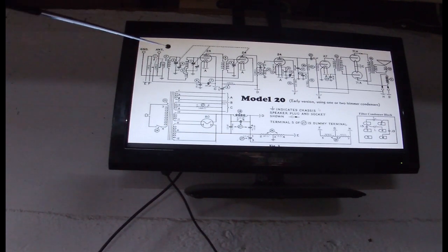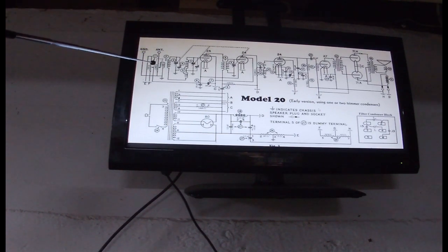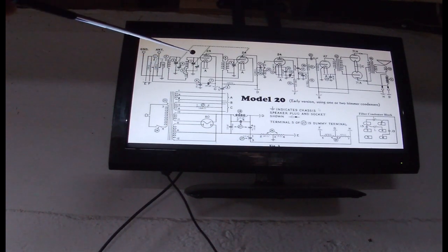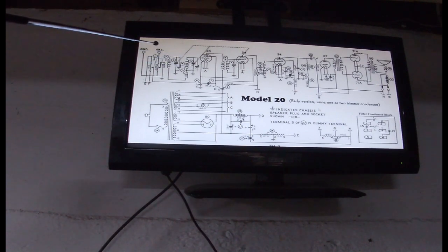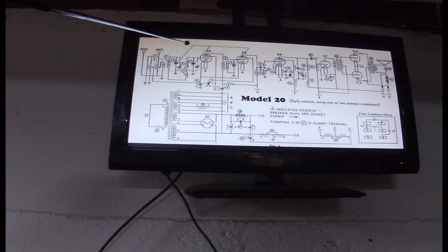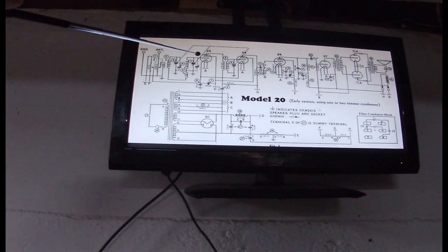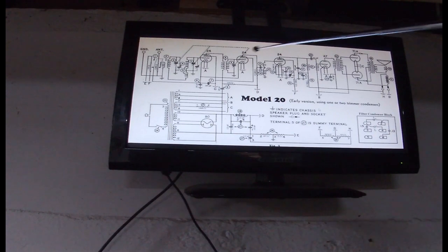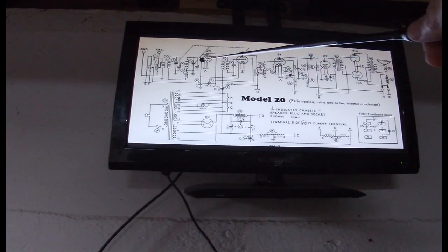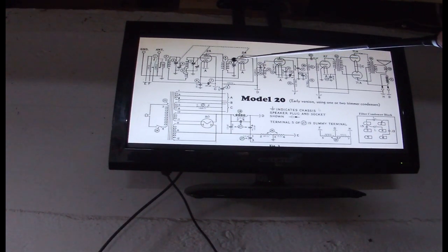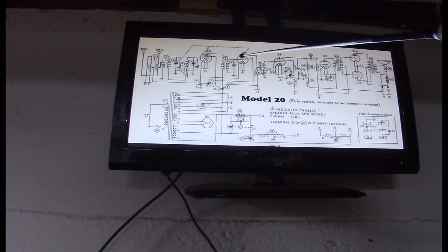So what we did was we put a signal here and fed it through this transformer here, and we were able to do it all the way up to here to the grid without the power on, because nothing here is powered up. So I put a signal in and checked it all the way to here without the power on. We had a good signal, and then with the power on, we had a lot of noise, but we had a good signal at the grid of this tube right here.